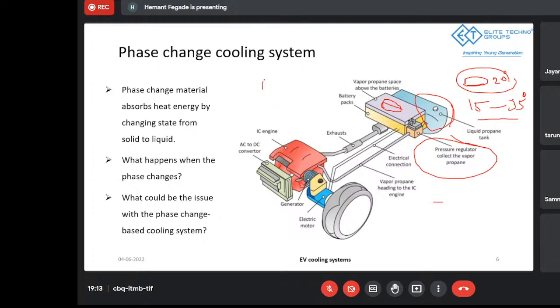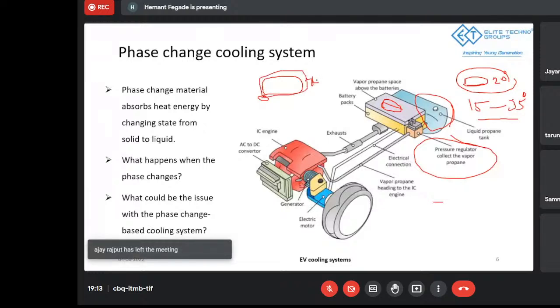With a single pass, if you're releasing or convecting X amount of heat from the battery pack, you need to maintain that. When coming back to the original source, you again cool it off, then recirculate, and it will still extract only X amount of heat. So you need to calculate this X amount of heat. That gives you a conclusive answer on what sort of coolant to use for dissipating it, since it depends on the thermal properties of the coolant and on the circulation system, as different circulation systems are tested for these scenarios.